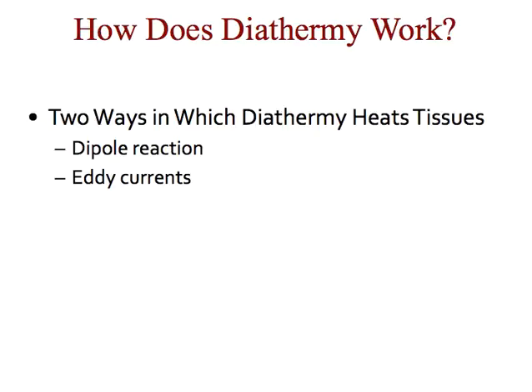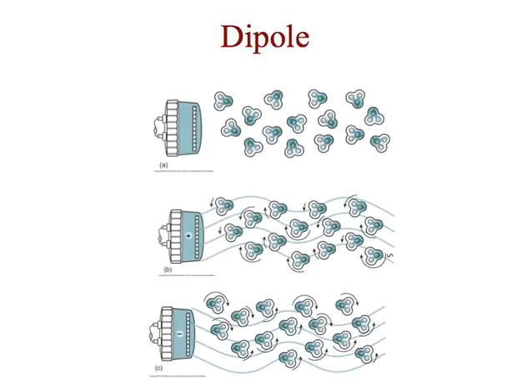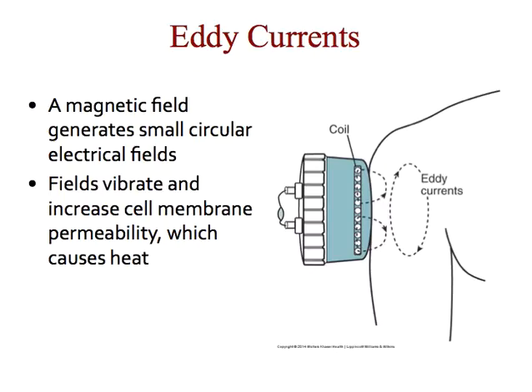There are two ways diathermy can heat tissue: the dipole reaction and eddy currents. In the dipole reaction, molecules whose ends carry opposite charges begin to rotate. The electromagnetic wave produced by the shortwave diathermy causes these dipoles to rotate, and as they rotate, friction occurs in the body and produces heat. The other method is eddy currents.